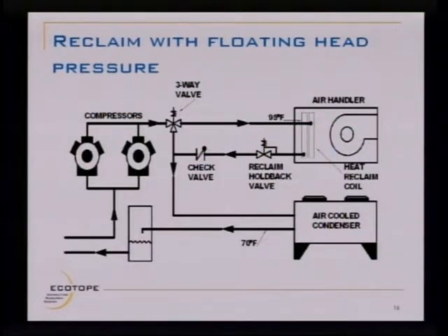So to do that, manipulation of the conditions in the air handler, what we do is we add what we call a holdback valve, a heat reclaim holdback valve, and that can then be set to raise the pressure in the coil when there's a call for heat and the refrigerant's going this way. You throttle the piping down to raise the pressure in this coil and raise the condensing temperature up to somewhere around 95 degrees so that you can get the refrigerant to condense in that coil. And then after it goes through there, it goes through the rooftop condenser and drops as much heat as it can before it goes back to be heading to the refrigerated cases.